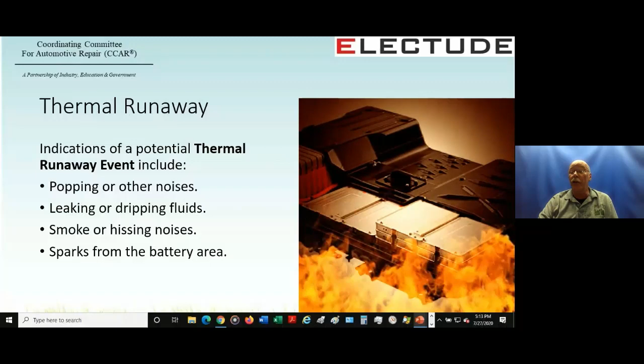So if you experience popping, leaking, dripping, smoke, hissing, or sparks in the battery area, you may be looking at thermal runaway. And because it's the gift that keeps on giving, there's no time limit on how long it takes for a thermal runaway event to occur. It could take weeks to occur after a collision or extraordinary event.